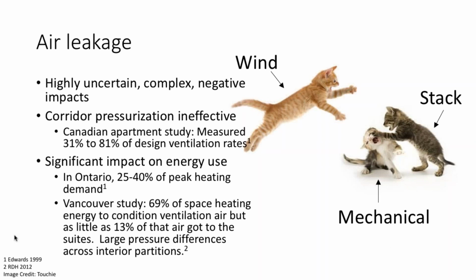One really interesting study in Vancouver looked at distribution of ventilation air through the building—this is a milder climate than ours, bear in mind. Almost 70% of the energy that went to space heating was used to condition the ventilation air, but only a fraction of that was actually getting to the suite. So we're wasting a ton of energy trying to condition this air, but it's not getting to the places where we need it to go.